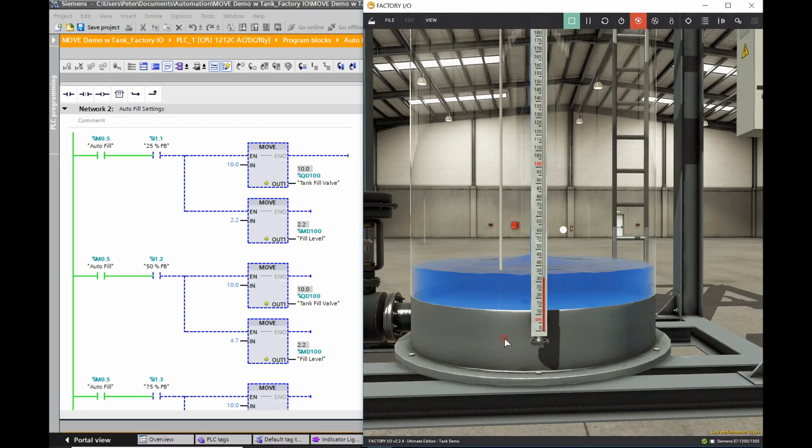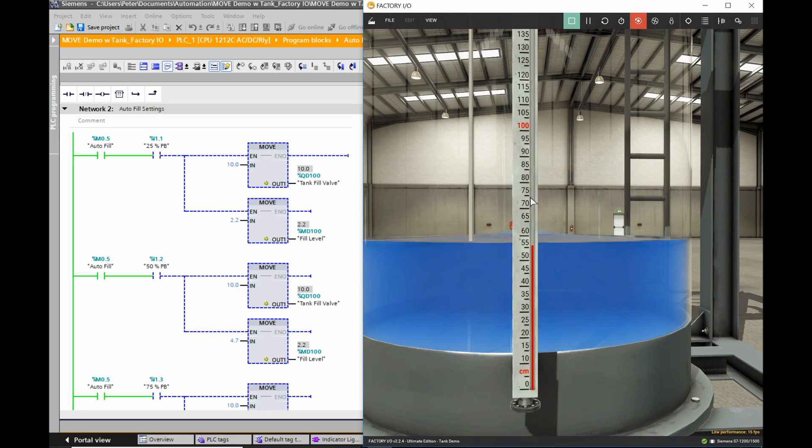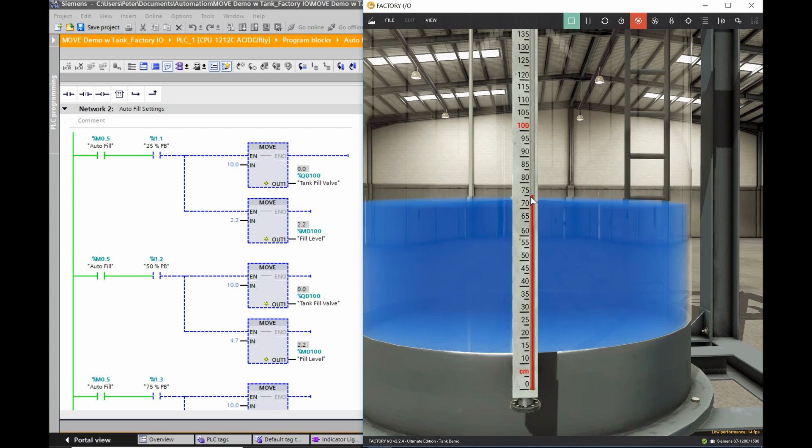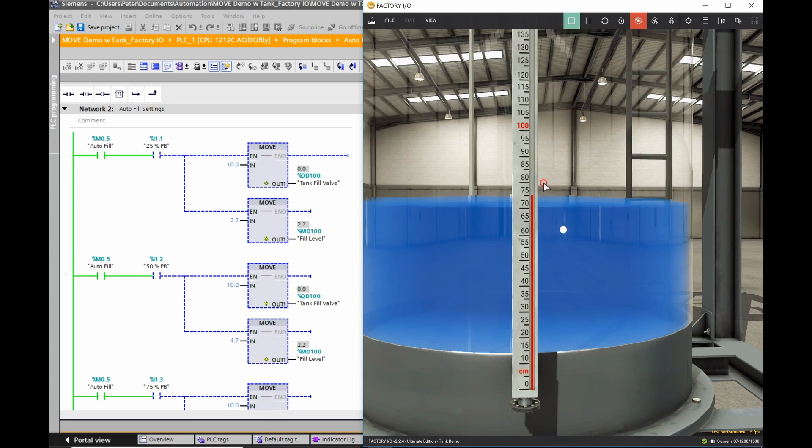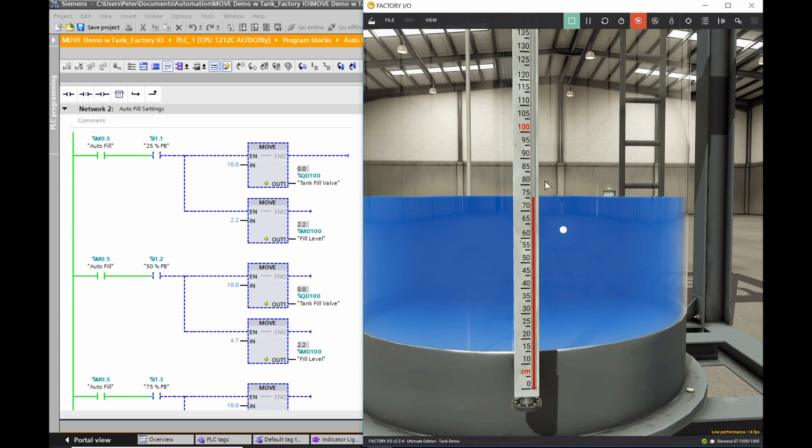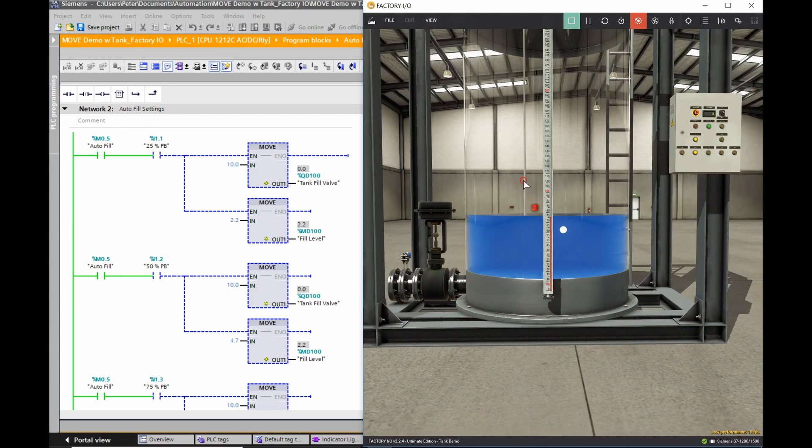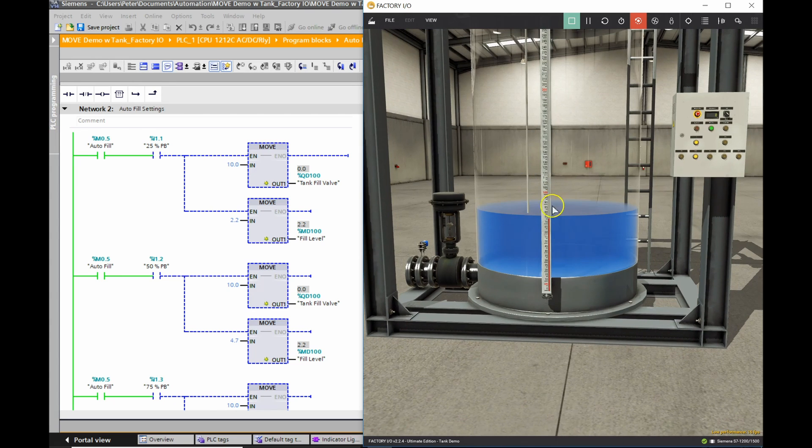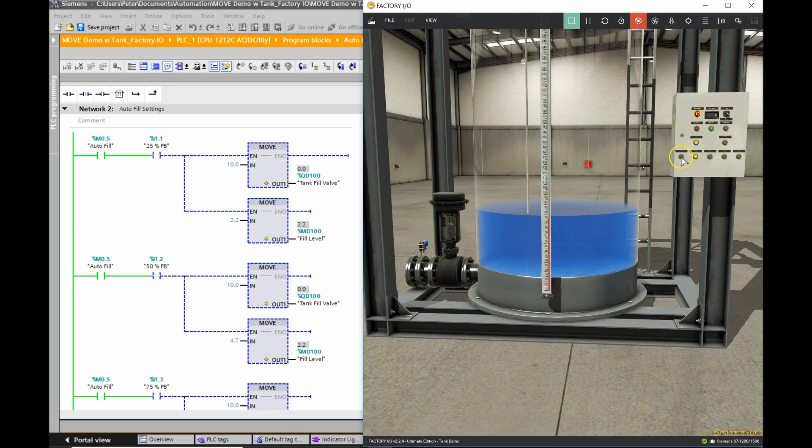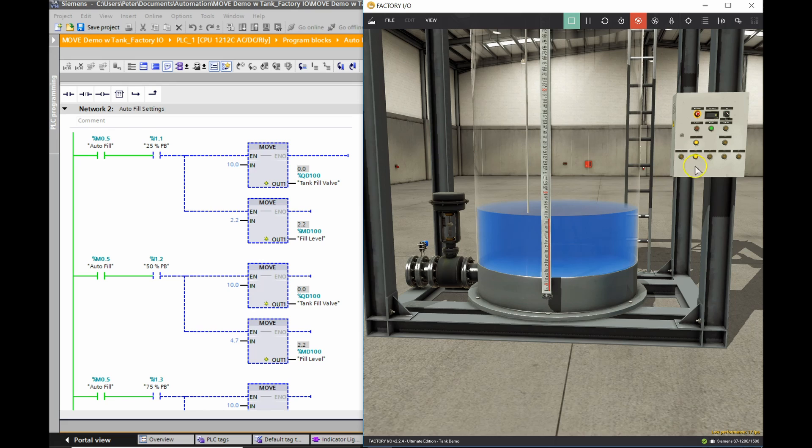I'll show you the program in depth in the next few videos. So we're at zero, we want to go to 25%. So we'll click this guy. And this guy will increase the level in the tank. At 25%, that should be 75 in our tank. And it stops basically dead on at 75. You may be able to hear the PLC clicking behind me. That is because as this settles out, I have a small range that I've created to look at the level in the tank. And within that range, I want this indicator light on. So as it ripples, it kind of turns the light on and off now. Once the level of the tank settles out, then my indicator light settles as well. Beautiful.